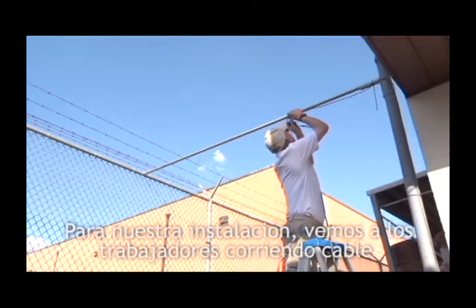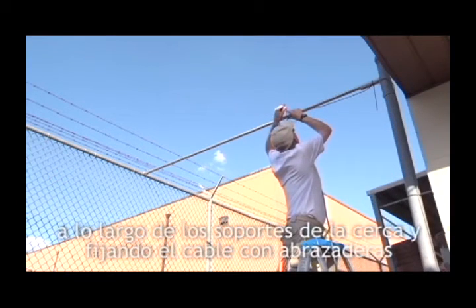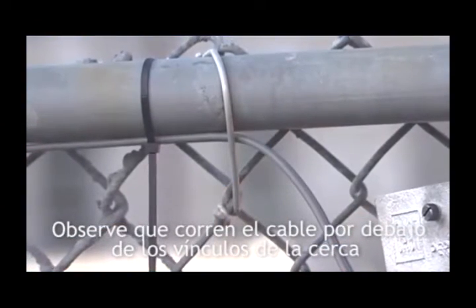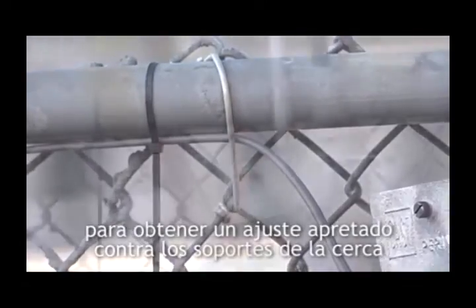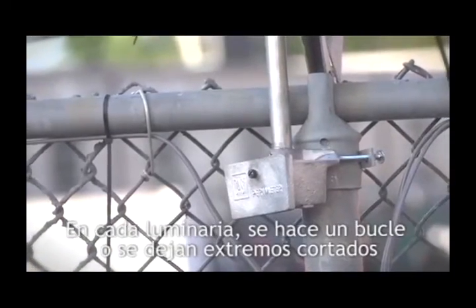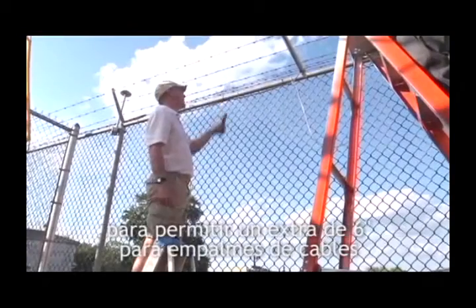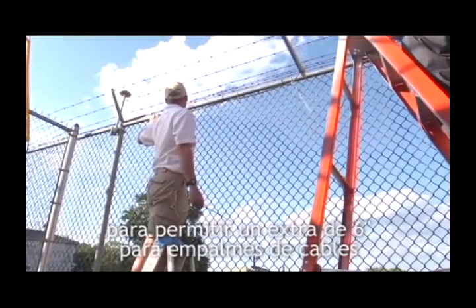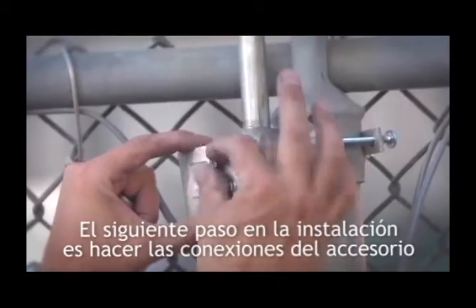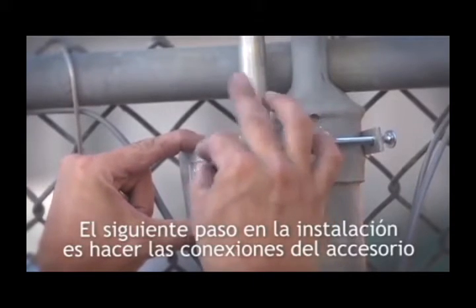For our installation, we see the workers running wire along fence supports and attaching the wire with cable ties about every 2 feet. Notice that they run the wire under fence ties to get a tight fit against the fence supports. At each fixture, a loop is made or cut ends are left to allow an extra 6 inches for wire splices. The next step in the installation is making the fixture connections.